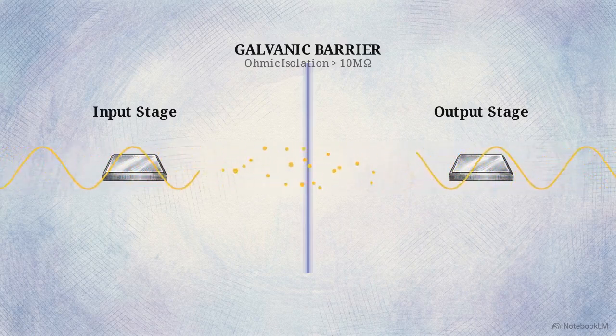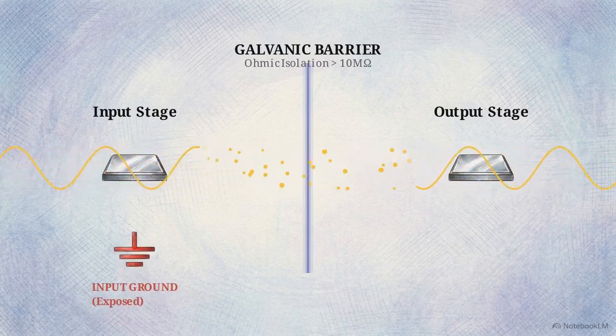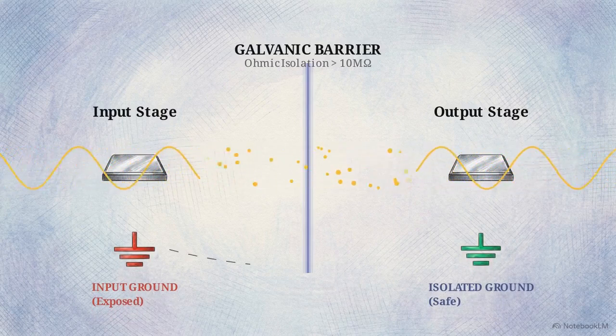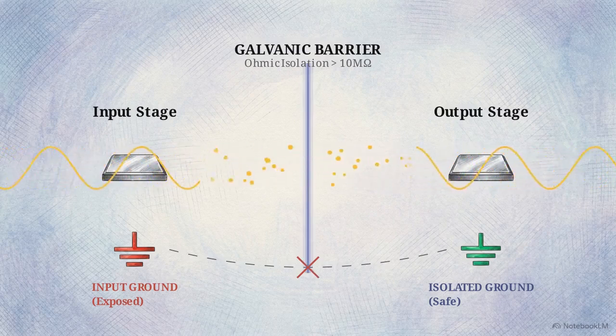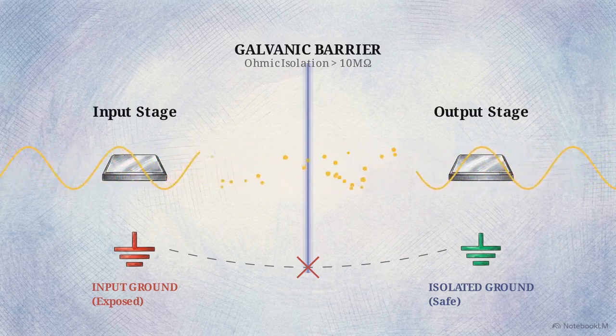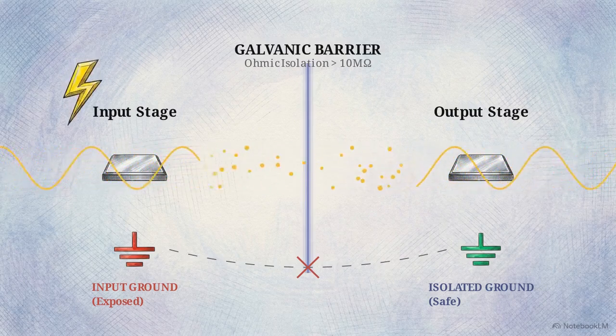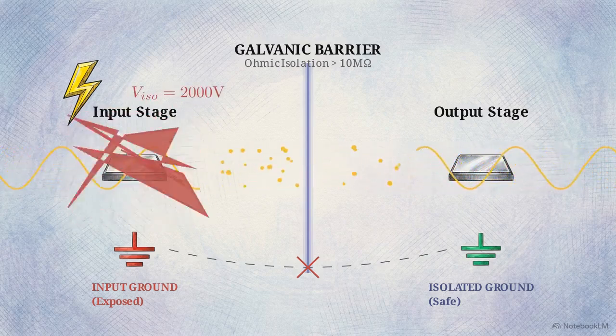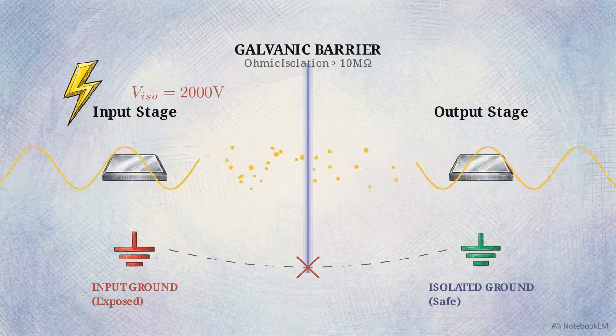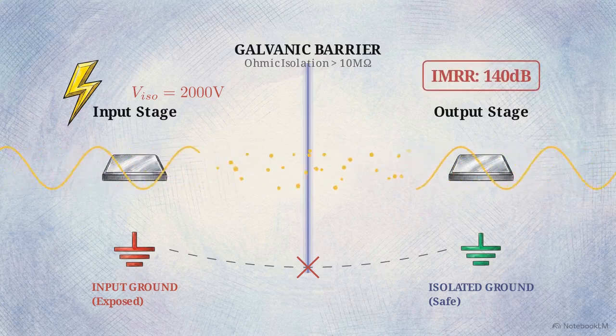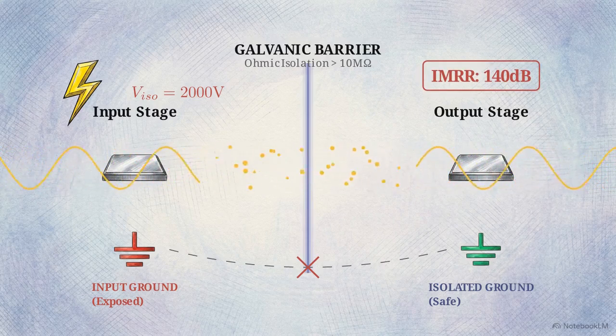This topology creates two completely separate grounds: an input ground exposed to the high voltage and a safe, isolated output ground. Hardware in this environment is judged by its isolation mode rejection ratio, or IMRR, which measures how well that physical barrier repels kilovolts of potential difference.